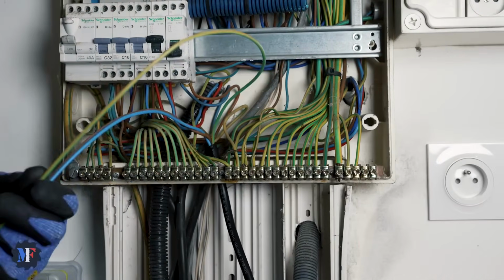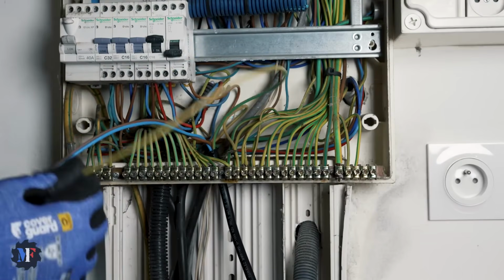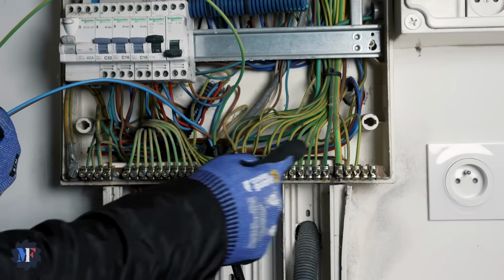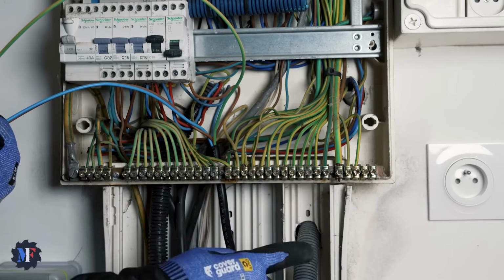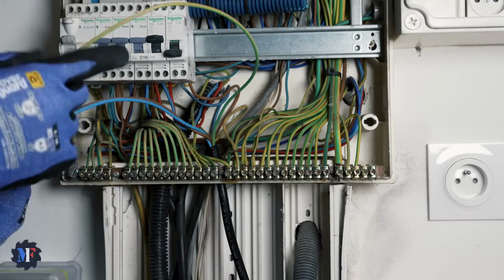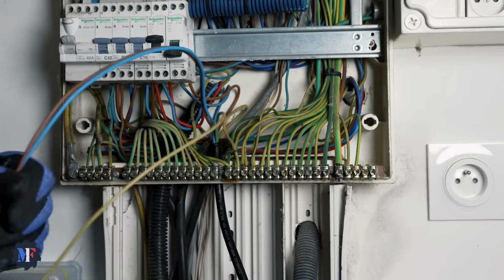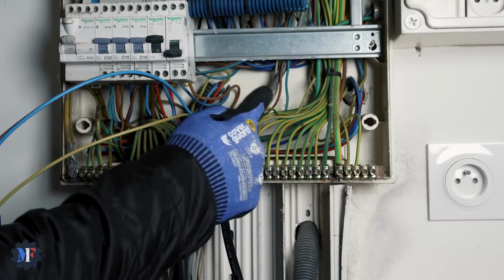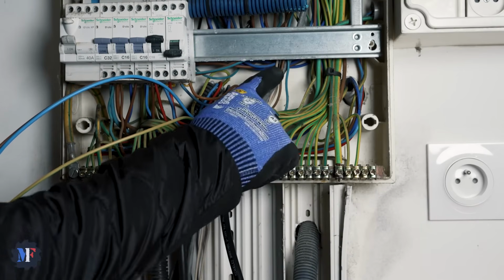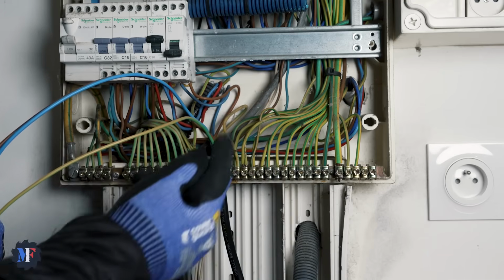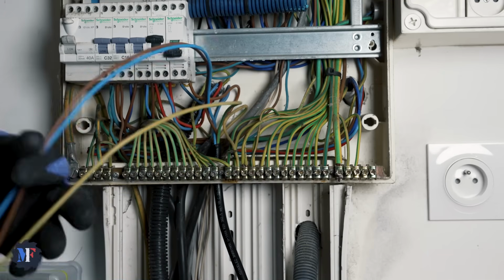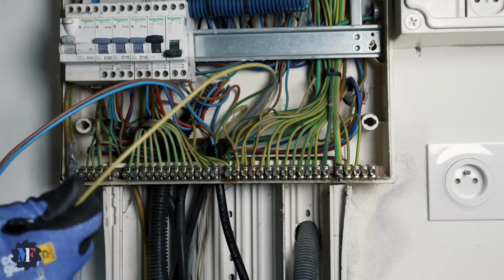So the 3G2.5 cable is stripped. I'll be able to take my ground wire, pass it behind the ground wires that are already connected, and tap in right here. Next, the phase and the neutral. It can be tricky because there are already quite a few wires. You have to run them behind the circuit breaker supports, go up to the differential breaker, and connect them. But for now, we're focusing on the ground.